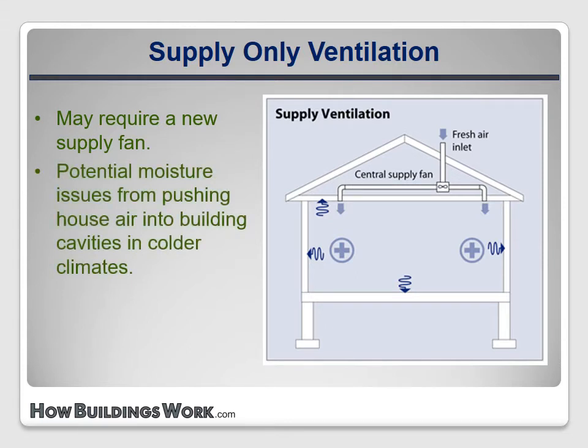Supply-only ventilation is another strategy. As you can see from the diagram, as the fan pushes fresh air into the house, it creates positive pressure. Wherever there are openings in the envelope, stale indoor air is pushed out. This could be done with a wall or attic mounted fan, but there are some issues with this approach. One is that house air is pushed into building cavities where it might cause problems, especially in cold climates. The other is that in the winter, cold outdoor air is introduced into just a few locations where it's likely to cause comfort issues. So this approach is rarely used.